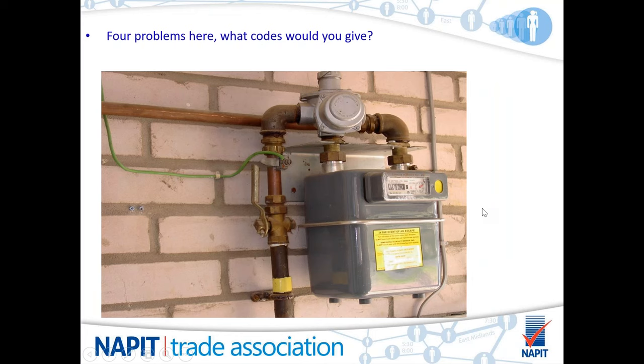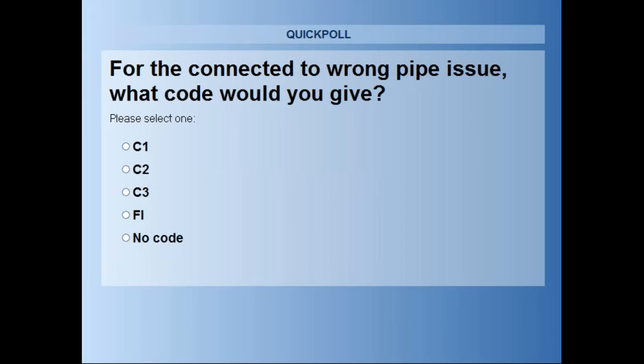What we've got on the presentation at this present moment in time is a picture, as you can obviously see. We've actually got a picture here that has four problems with it. And we have a poll now for you to have a go at seeing if you can come up with what code you would give to these problems. The first one, as you will obviously see, is that the protective bonding conductor is connected to the incoming service and not to the customer's installation pipeline. So maybe we could have your ideas of what code you would put onto it.